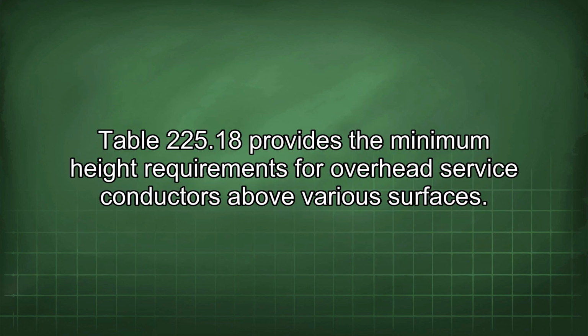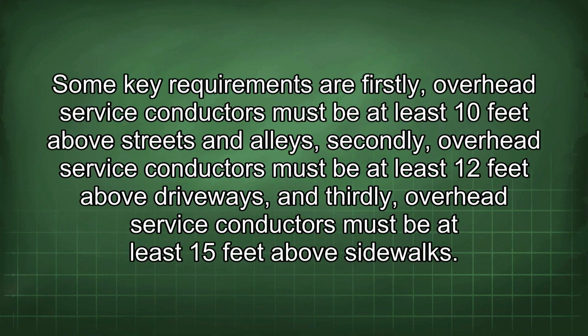Table 225.18 provides the minimum height requirements for overhead service conductors above various surfaces. Some key requirements are: firstly, overhead service conductors must be at least 10 feet above streets and alleys. Secondly, overhead service conductors must be at least 12 feet above driveways. And thirdly, overhead service conductors must be at least 15 feet above sidewalks.